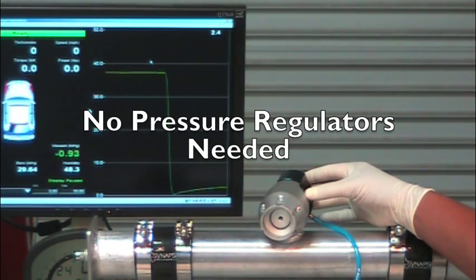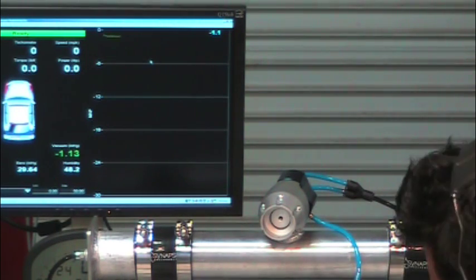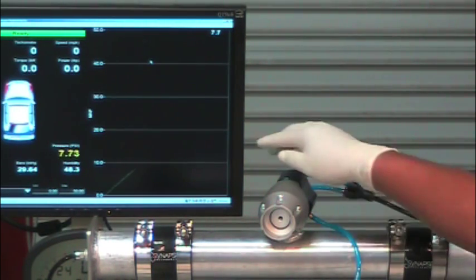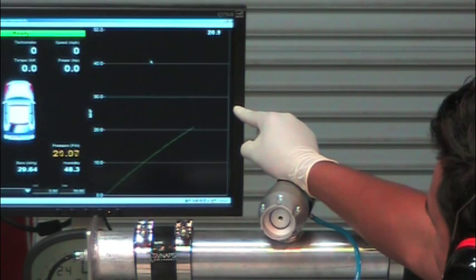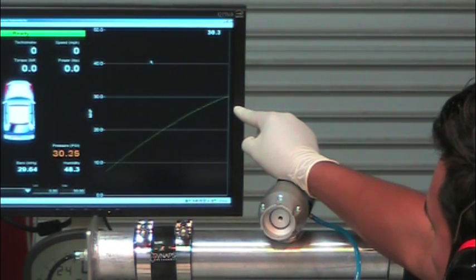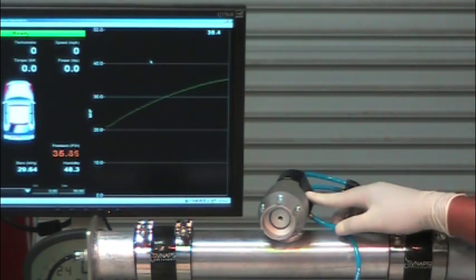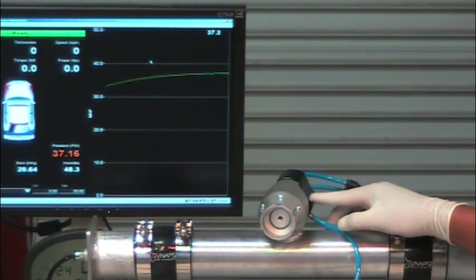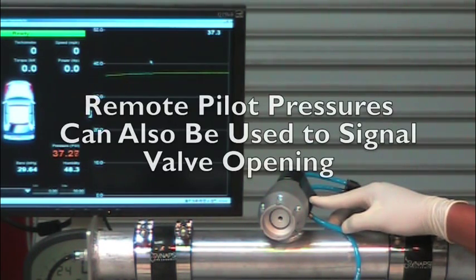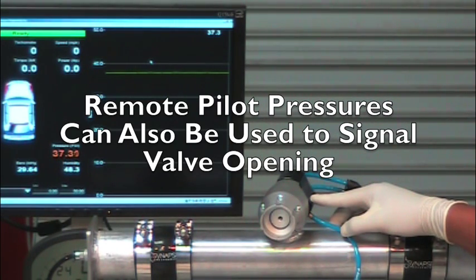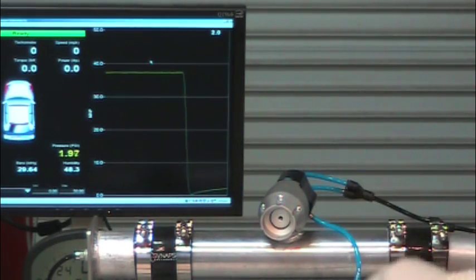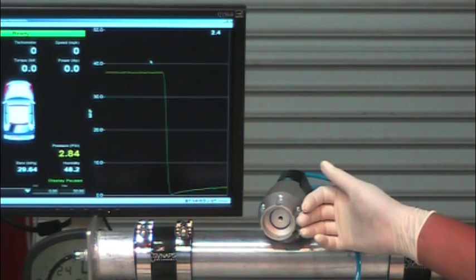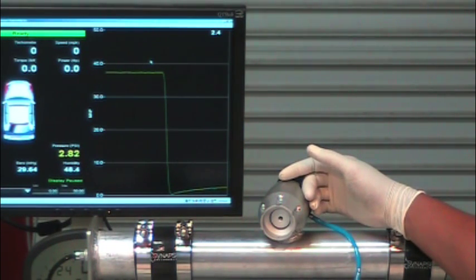So the same pressure that's already in the vessel will not only keep the valve closed at all times, but if that pressure rises in the system, that same system pressure can actually actuate the valve to relieve that pressure and leave that valve open if it needs to.